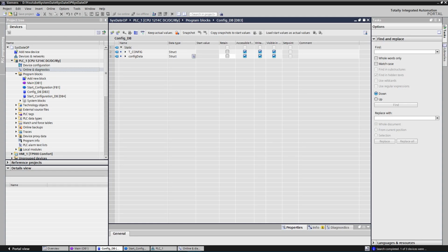Let's switch to our configuration data block. As I already mentioned, the configuration data block structure is as follows: header and subfields. The data type of the header is IF_CONF_HEADER. You need to write that data type by hand and all the necessary fields will show up automatically. Supported subfields are IP of the station, PROFINET IO device name, and network time protocol. In this demo, I am using 2 out of 3: IP address and PROFINET IO device name.